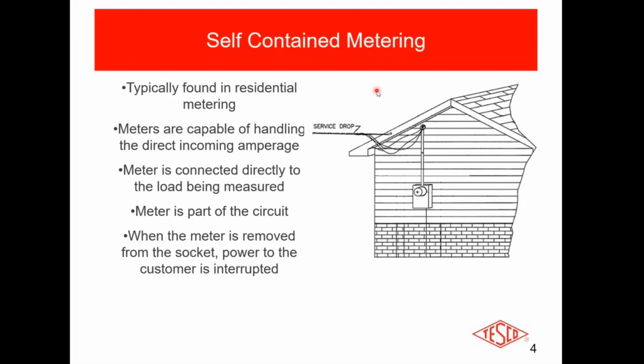Now, if you use horn bypass jumpers, you don't have to kill the service, but basically you would have to jumper around it because the meter is part of the circuit, all right? And it is connected directly to the load being measured. Most of our meters are class 200, meaning that they can handle 200 amps. There are class 320s, which can handle 320 amps. Okay, that's your basic self-contained metering.